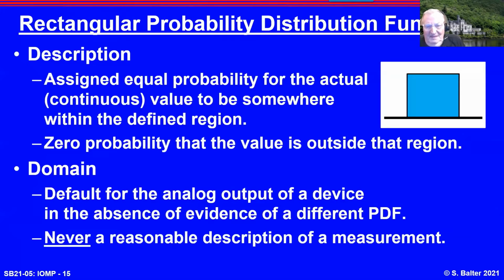The machine has an output. We don't know what that is. For convenience, we assume the output of any source is a rectangular distribution. It's somewhere within the box and 0 outside the box. This is, in metrology, the default for the analog output of a device, unless you have other information. If you're looking at the output of a guitar, it would be 6 peaks around each of the 6 strings. It's never the description of a measurement.